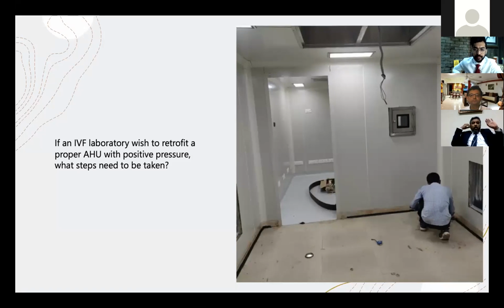To set different pressure levels in different rooms, you need different AHUs or different air control units. Ideally, the highest pressure level should be in the ICSI lab or IVF lab, the next level in the ICSI OT or aspiration area, and the lowest level in the corridors.